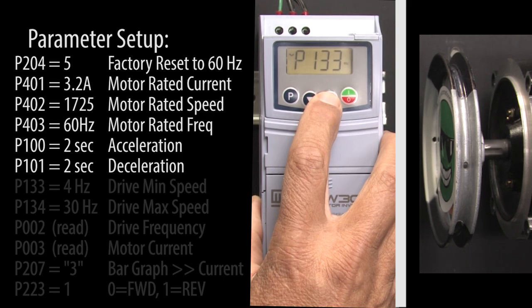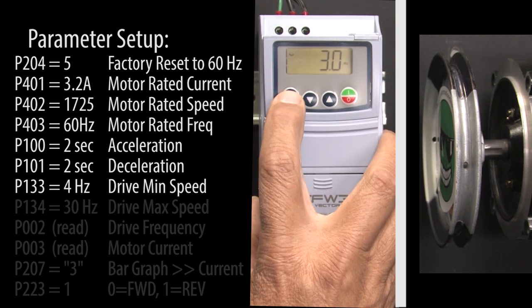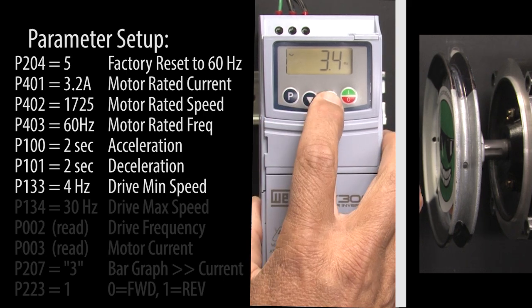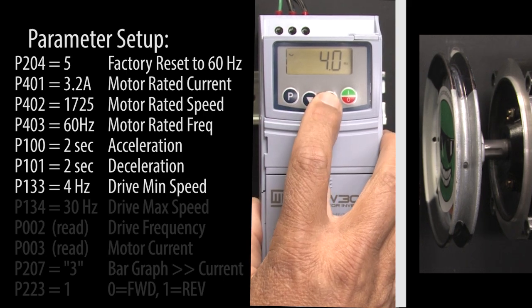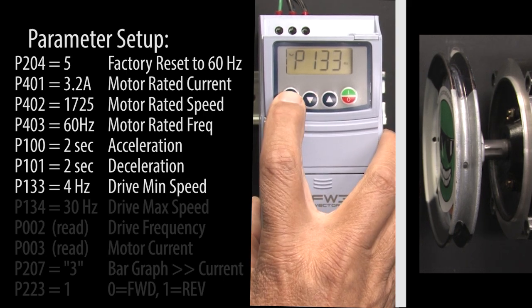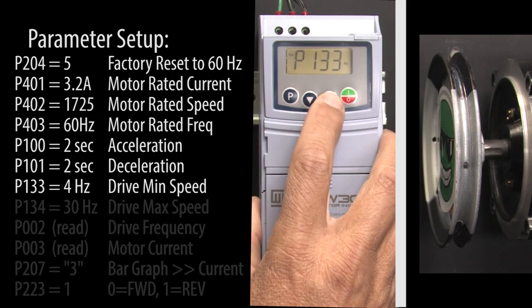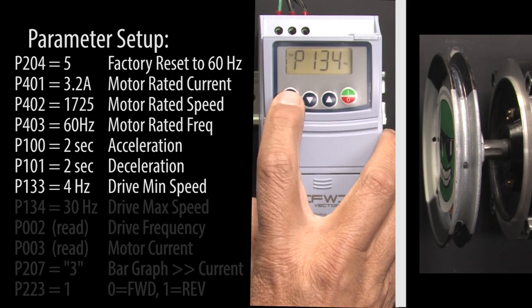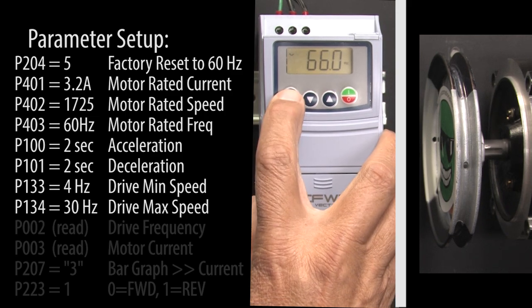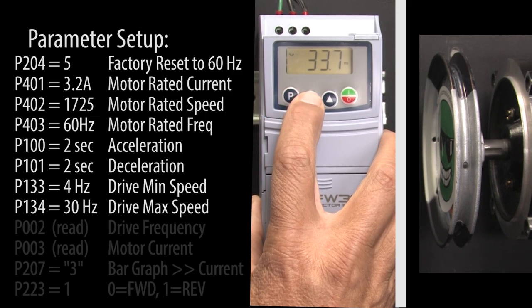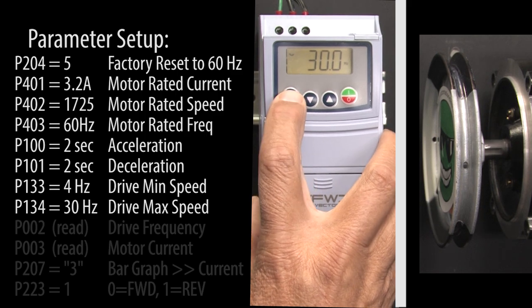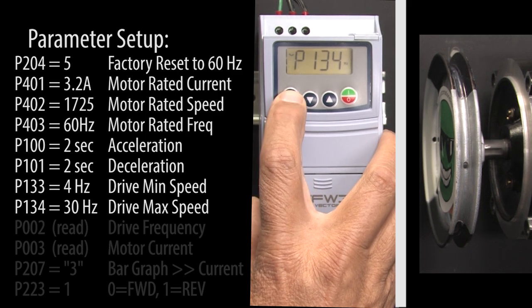Scroll to the min speed parameter — let's make that 4 Hz. Hit P to accept that. Scroll to the max speed parameter, hit P, let's change our max speed to 30 Hz. Hit P to accept that.